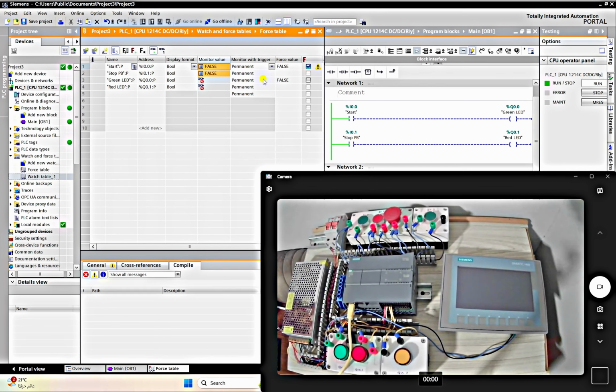And usually engineers will force inputs or outputs when they do a bypass. And in the companies that I worked at, if you're going to do a safety bypass or something like that, then you need signatures, and there is a form that you need and a process that you need to follow in order to do that. And one requirement is to have the signature of at least two engineers, the safety one and the manager of controls engineers, so they can make sure that this is safe. Okay, so this is not a joke, guys.